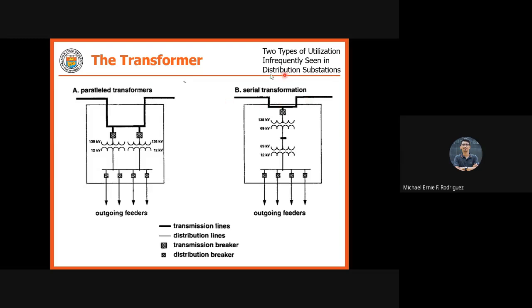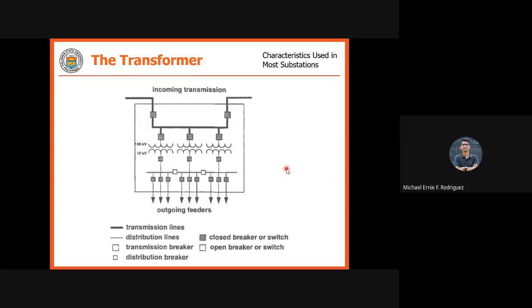And then we have serial transformation, which we rarely see. Let's say we have a transformer stepping down from 138 kV to 69 kV, and then another transformer which steps down 69 kV to 12 kV. This is not commonly used: two transformers in series, with two voltage transformations, from 138 to 69 kV and then from 69 to 12 kV. So these are the characteristics most used in most substations.